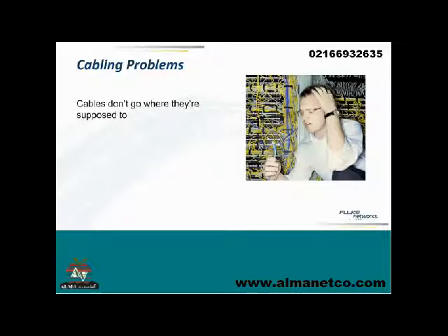Okay, let's talk a little bit about cabling problems. We did a research exercise a few years ago to find out what the biggest cabling problems were. We found it kind of amusing because we make a lot of complicated test equipment that helps you figure out all sorts of complex cabling problems. The funny thing is the biggest problem is cables don't go where they're supposed to. They're not labeled properly, and they don't go where you thought they went. You unplug something and you try to plug it back in and it no longer works because it was labeled wrong. So this is the number one problem.